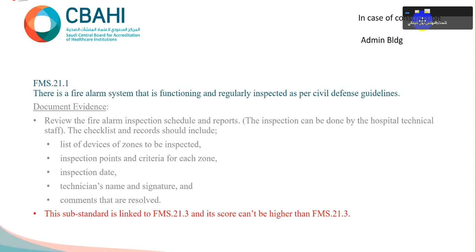If we don't have PPM and observation reveals that the control alarm system or fire alarm system control panel is faulted, then we will get 0, unfortunately. As observation, we have to inspect the functioning of the fire alarm system. How? We should visit the control panel and make sure that no fault is existing, like this case here. And if you see here on the right side, one of the, I don't know whether medical record or store, but unfortunately the smoke detector was covered by the plastic cover.